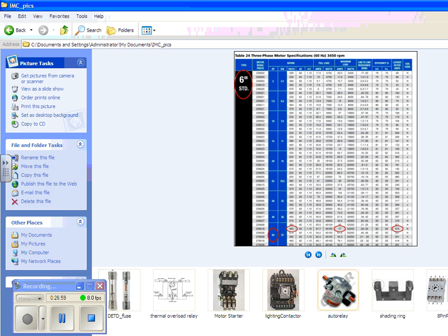So if you're using a size 8 starter, that's one big motor. Now the smallest one is not 00. Don't go in the wholesale house and say, I would like a 00 motor starter. No, you want a double aught. A double aught motor starter is the smallest size by NEMA standard. Single aught or 1 aught is the next larger one, and larger than that is 1.